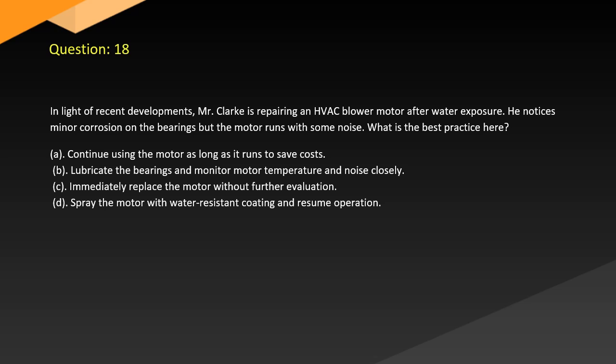Question 18. In light of recent developments, Mr. Clark is repairing an HVAC blower motor after water exposure. He notices minor corrosion on the bearings, but the motor runs with some noise. What is the best practice here? A. Continue using the motor as long as it runs to save costs. B. Lubricate the bearings and monitor motor temperature and noise closely. C. Immediately replace the motor without further evaluation. D. Spray the motor with water-resistant coating and resume operation.